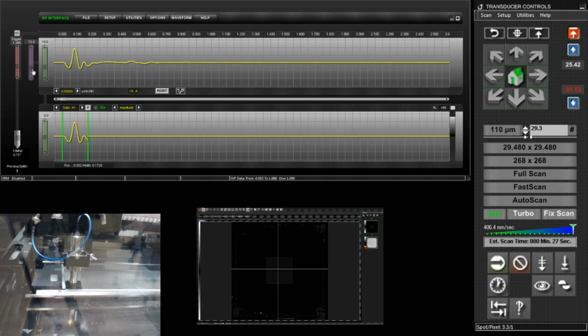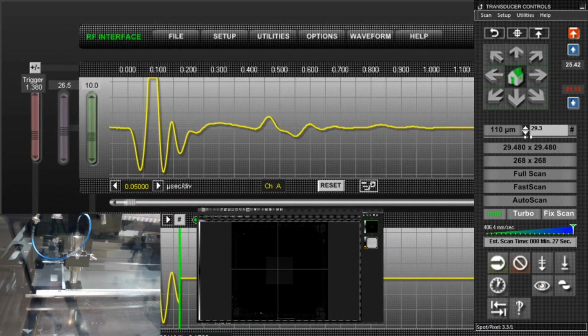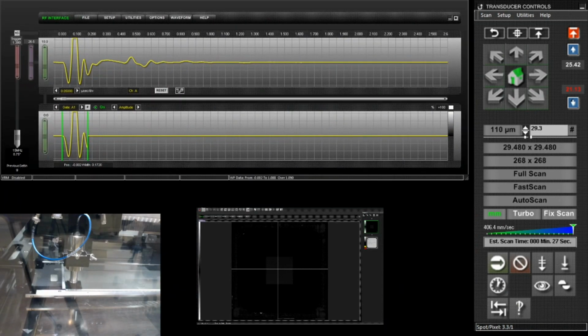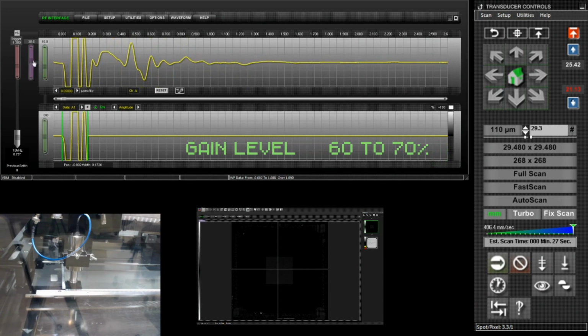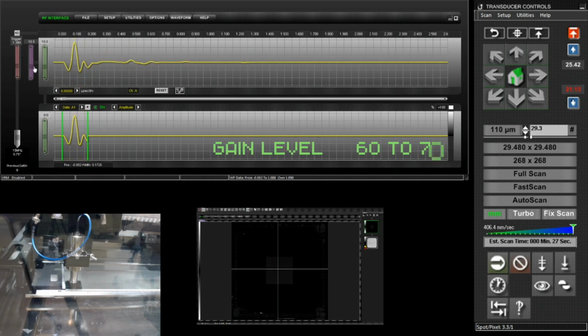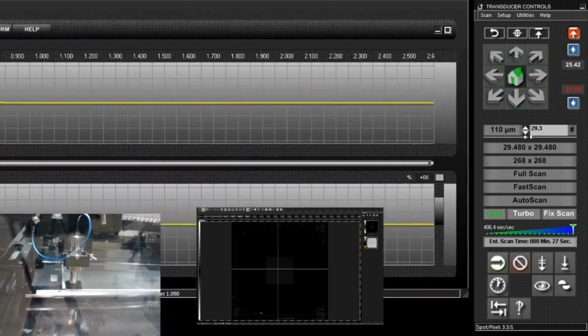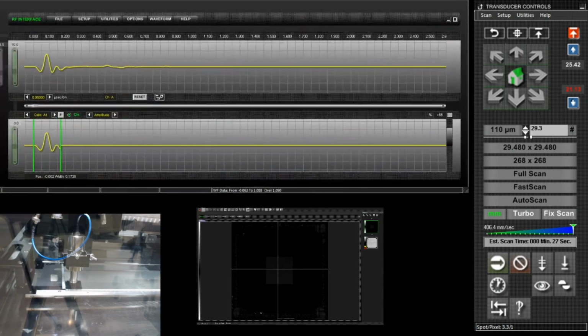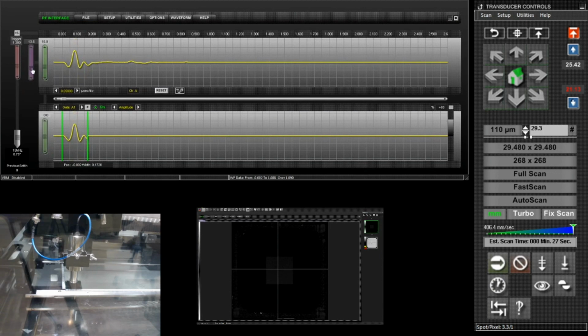The third thing is adjust the gain. So the gain control is this second sliding bar here on the RF interface. The right side, or the green one, is the secondary gain. We're just going to be using the front end gain. Typically you're not adjusting this one unless you're using 2 channels, doing through scan, or using extra options that we're not using right now. So for now, just use the front end gain adjustment. So what you're looking for is to adjust this until the semi-scan scale, which I'm about to show you on the right side here, is around 60 to 70%. I've got it on 66. So you want to adjust that until that's between 60 and 70%. Is a good starting point.